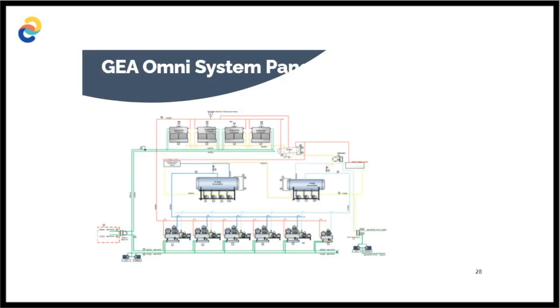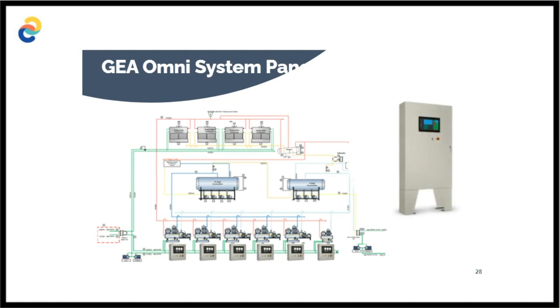I mentioned GEA is more than a compressor controller, so we can add the Omni as a system panel, whereby we can connect all the compressors and we can start to connect other features of the plant. So pumps, condensers, and even air coolers. And we do that by a feature called the smart connection box. So on each of these individual components, we have a smart connection box which takes in data and delivers that to the Omni system panel.